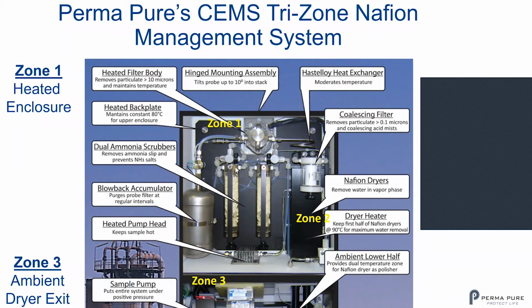This is very important because this cleans the sample for the next phase, which is our dual ammonia scrubbers. If we're on an SCR system and there's excess ammonia slip coming through into the sample gas, these ammonia scrubbers are going to strip out the ammonia before the sample is placed into the dryer.